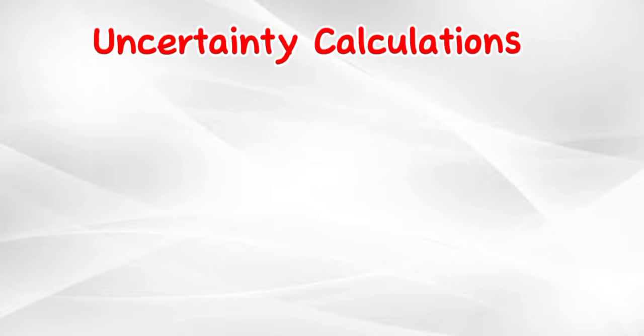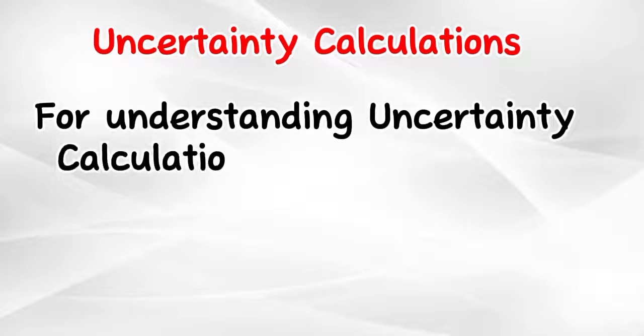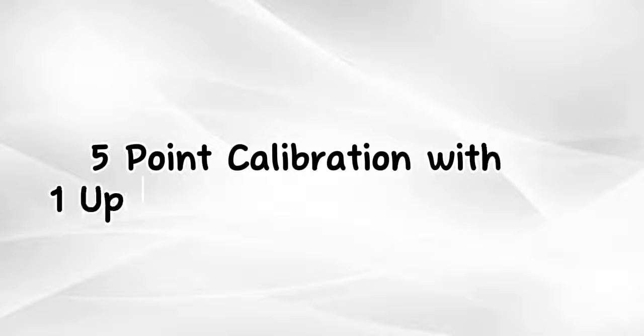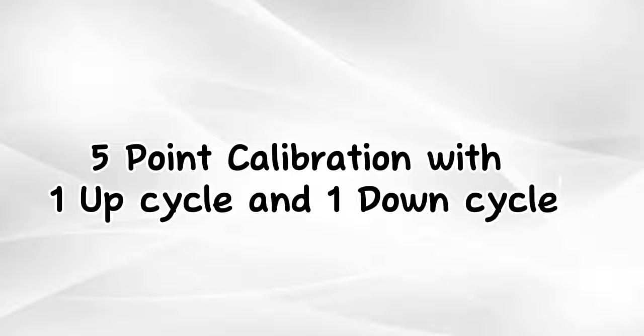For understanding uncertainty calculations, we will take an example of pressure gauge calibration: five-point calibration with one up cycle and one down cycle.